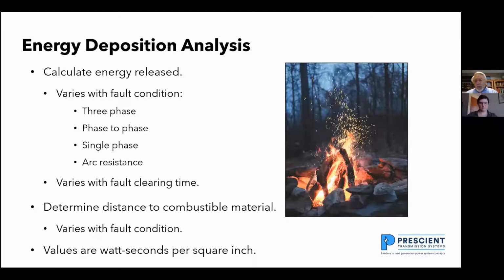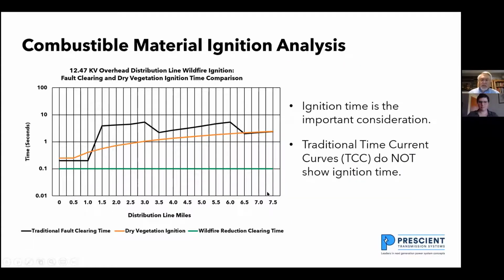So we want to calculate the energy released with fault condition. We do a calculation for three-phase faults, phase-to-phase, single phase. We include arc resistance, and the amount of energy that you release varies with clearing time. But varying with clearing time doesn't really demonstrate how well you're doing. A much better example is right here where I'm putting, instead of time, distribution line miles, and I'm comparing the ignition time as a function of mileage.